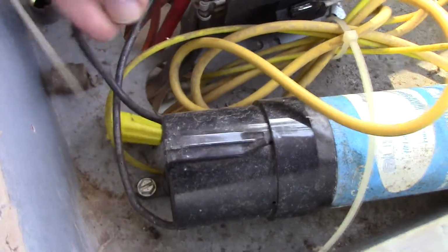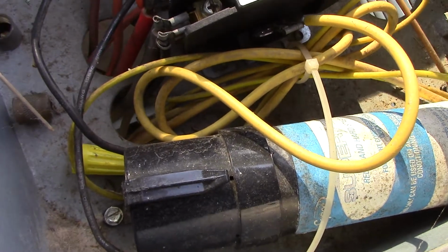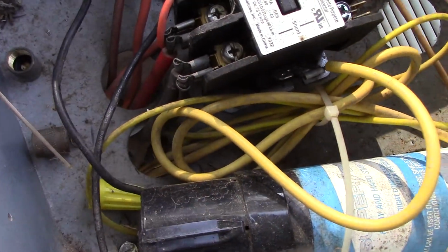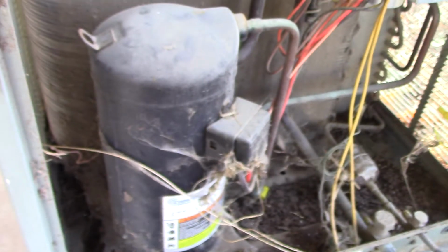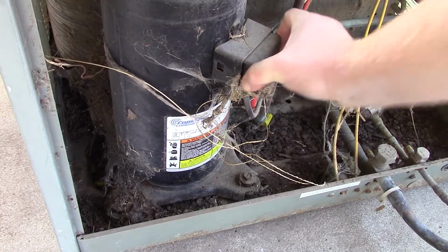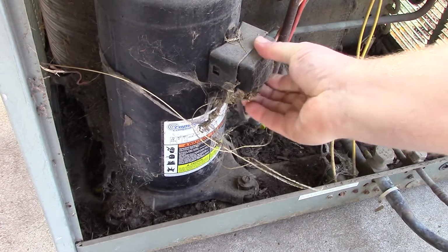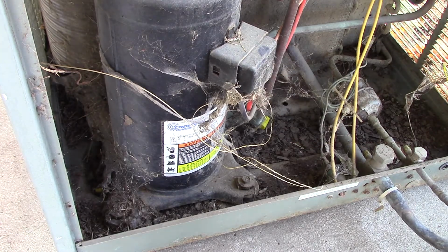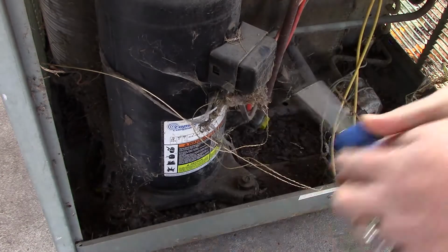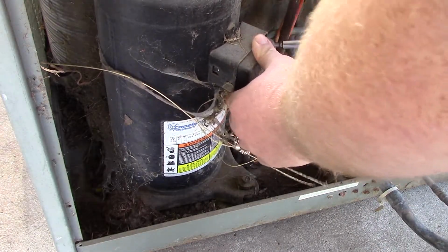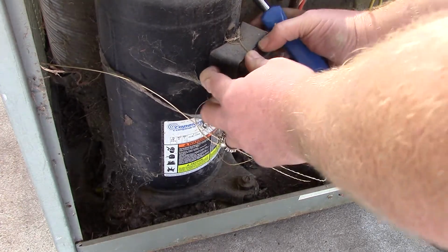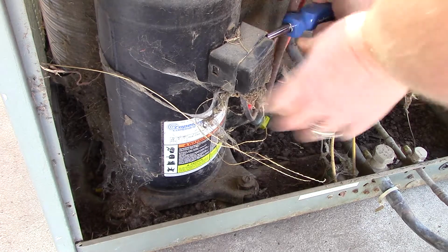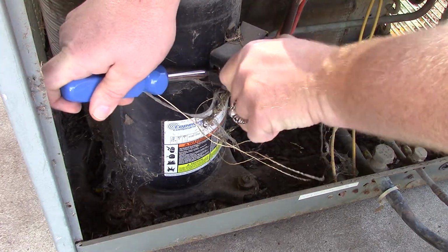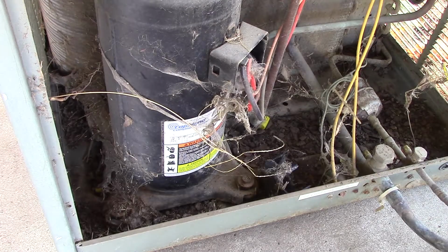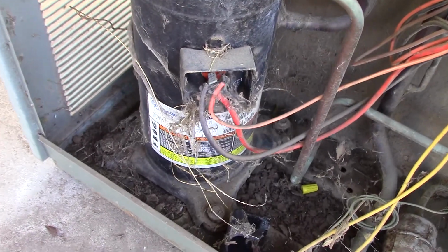You can pull these wires off, pull that wire off, and ohm out the compressor that way. The problem with doing that is, well, you have this box right here on the compressor. On this box, of course it wants to be difficult. Behind there is your wire terminals. Just like that. That is where you want to troubleshoot your compressor.